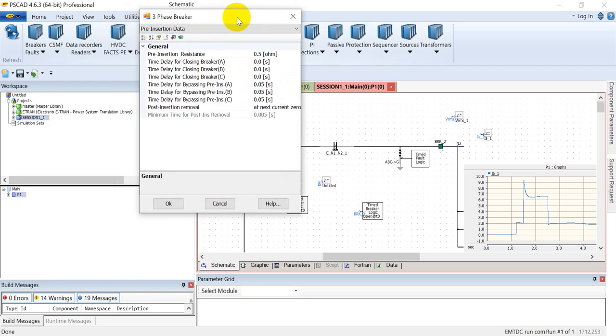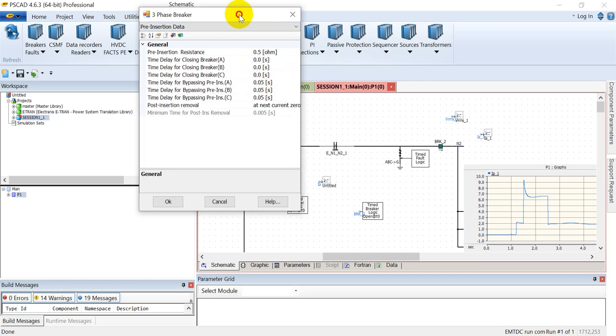You can add the closing delay in the circuit breaker. Normally in extra high voltage circuit breakers like 132 kV or 220 kV, we have a closing delay of roughly from 30 milliseconds to 60 or 70 milliseconds. So you can actuate that actual scenario by adding time delay for the circuit breaker.